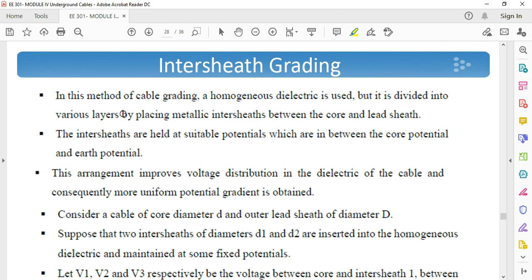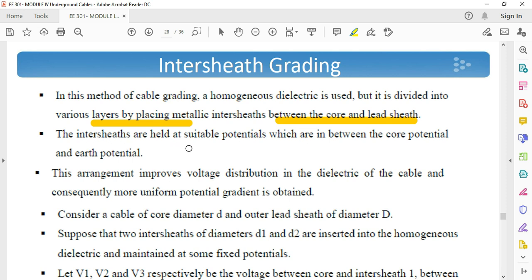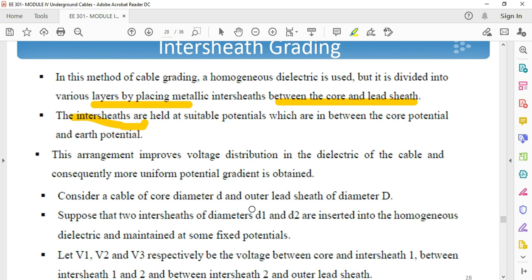Now we have intersheath grading. In this method of cable grading, a homogeneous dielectric is used but it is divided into various layers by placing metallic intersheaths between the core and the sheath. The intersheaths are held at suitable potentials which are in between the core potential and earth potential. The homogeneous dielectric material is used but intersheaths are provided in between, improving the voltage distribution and making the potential uniform. We can consider a cable with core diameter d and outer sheath diameter capital D, with two intersheaths of diameter d1 and d2 inserted.